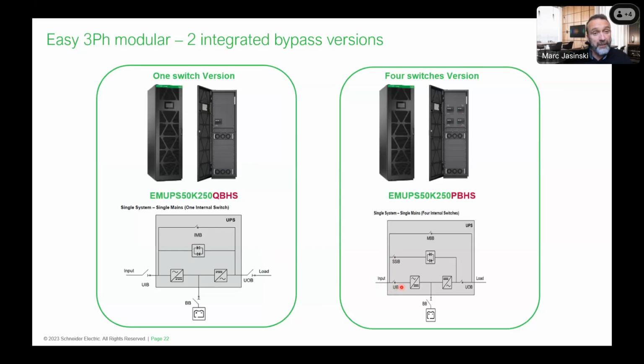As this UPS is fully modular, it was easy for us to integrate one solution with 1 bypass and the second one with 4 bypass. In terms of functionality, there is a little bit more flexibility to operate with the intervention or maintenance with a 4 switch bypass versus a single switch bypass, because as you can see, you can easily disconnect the full electronic part from the voltage using the 4 switches. However, as explained by Martins, this UPS is fully live swappable. Most of the components are live swappable, meaning I can replace the power module, I can replace the static switch, I can replace the display and potentially, soon, the main controller of the UPS, without having to move the UPS on bypass. So this manual bypass will not be used so often with such a conception and design.